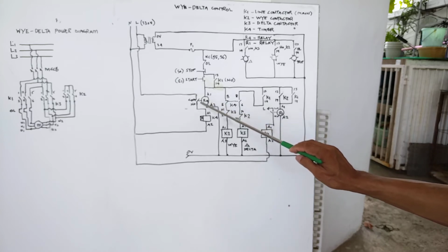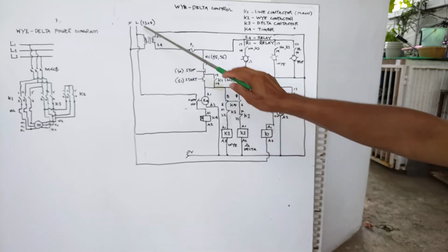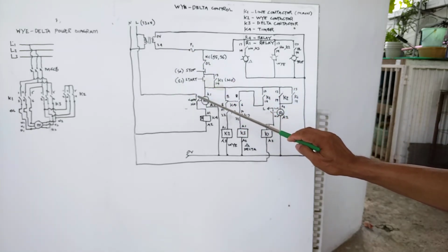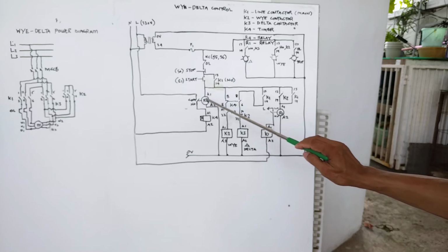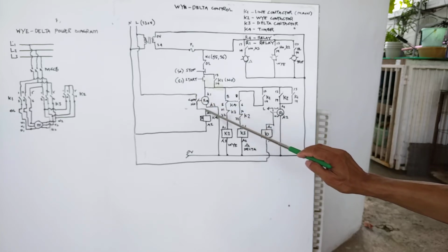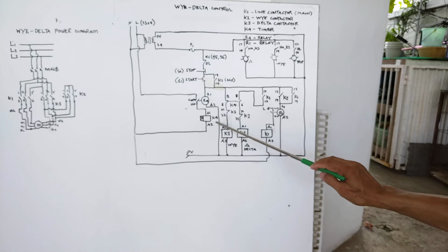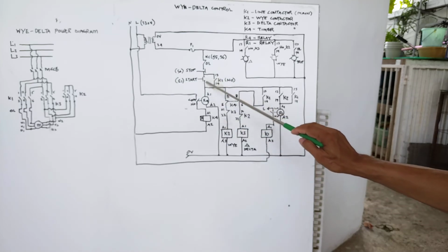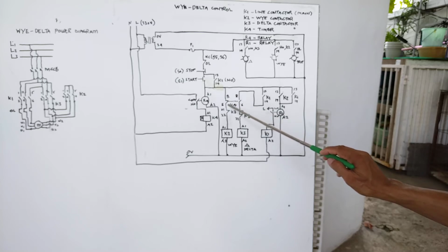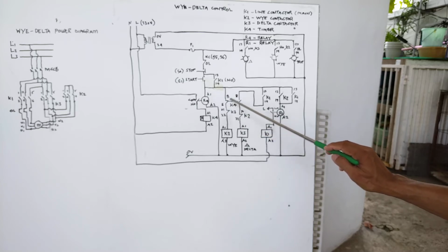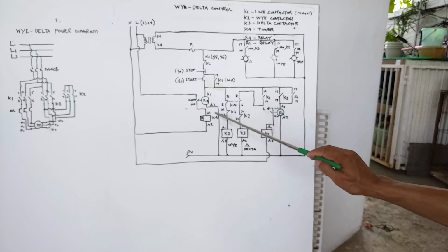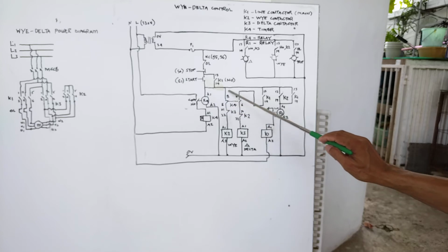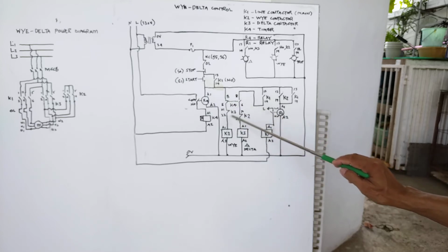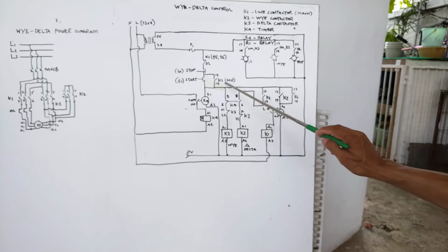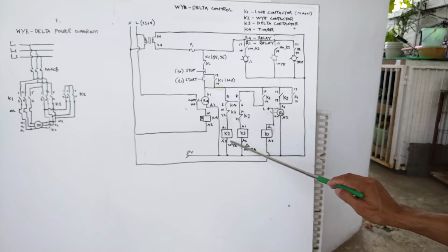Then I'm using one contact here, the common, the line will be connected there. When this one is energized, the normally open contact will close, then 220 will flow to A1, and the A2 is connected to the neutral line, so this timer is energized. Next, 24 volts can also come here, since this is closed. This is the timer, with normally closed and normally open contacts. Since the timer is energized, it will wait for the time delay set in the timer, so this one is still closed. Then K3 is not energized, meaning this is closed. So 24 volts will come here, then this one will be energized.